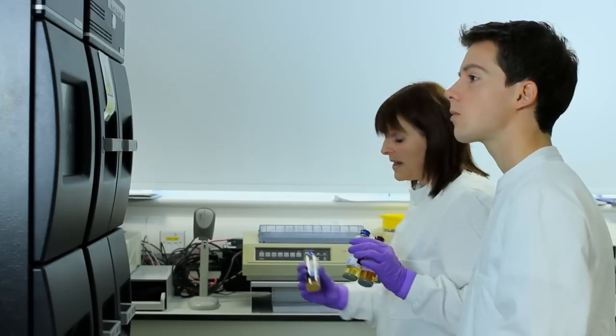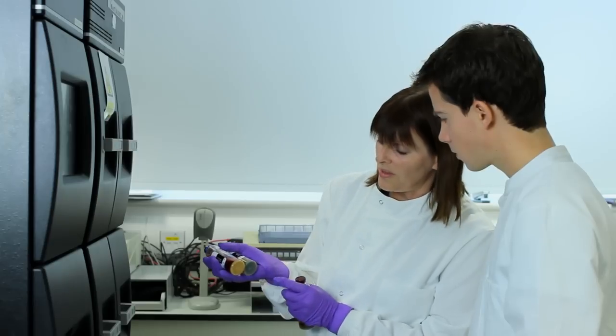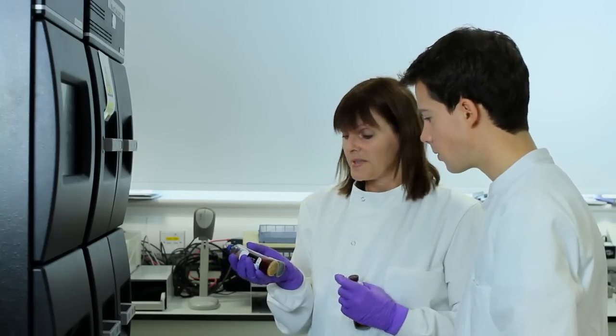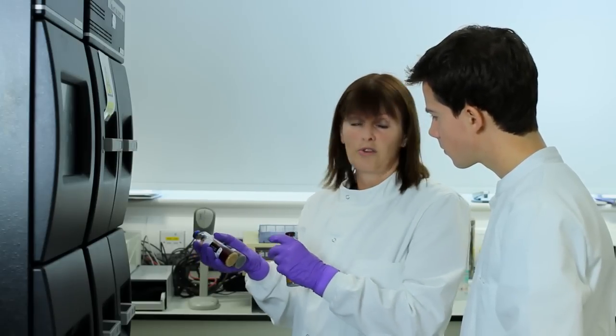As bacteria grow, they produce carbon dioxide and they change the pH of the bottom of the bottle. So what you've got there is a nice yellow colour. More acidic or more alkaline? That's more acidic. Okay, right. So they've actually done that. And because bacteria take about 20 minutes to reproduce, you can get a good reaction in about 4 hours on this machine.